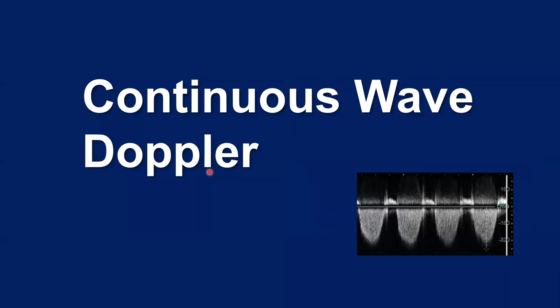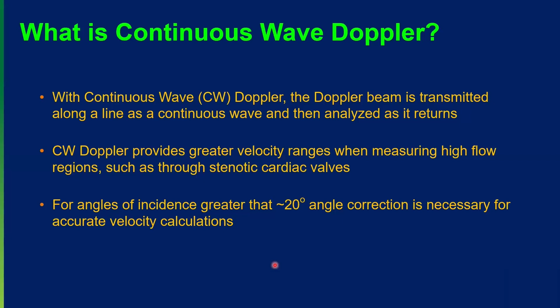What is continuous wave Doppler? In continuous wave Doppler, the Doppler beam is transmitted along a line as a continuous wave and then analyzed as it returns. Continuous wave Doppler provides greater velocity ranges, so we avoid aliasing when going through very high flow regions such as stenotic cardiac valves. They can get well over a meter and a half, even 2 meters per second sometimes, and some of the regurgitant flow can get even higher than that. So we need continuous wave Doppler to accurately measure those. If the angle of incidence is greater than 20 degrees, which is generally not the case in cardiac imaging, then we would want to do angle correction to get correct velocities.